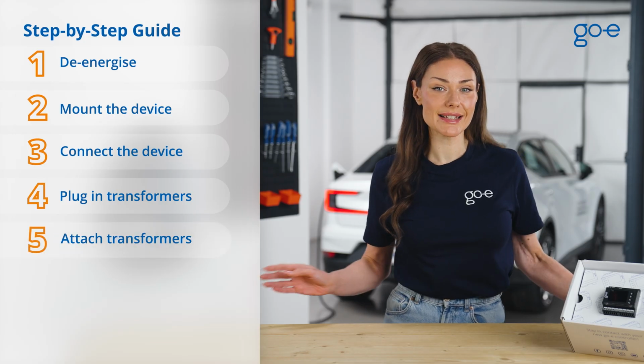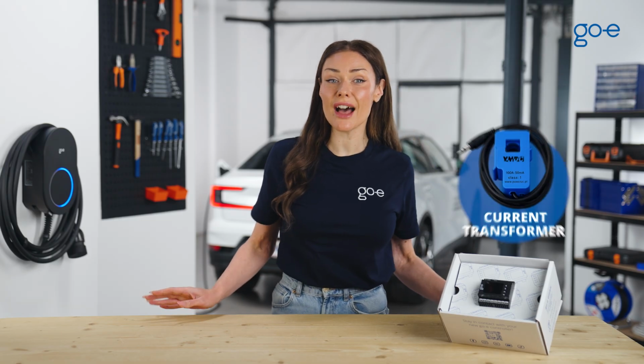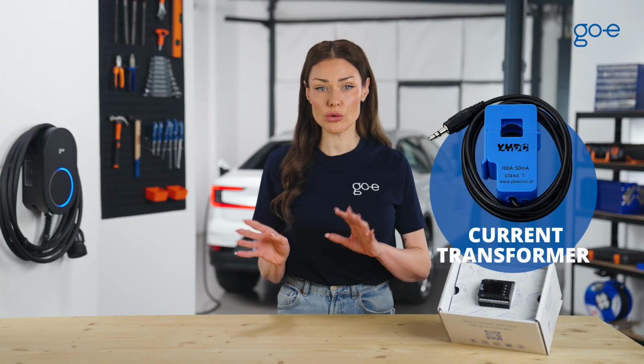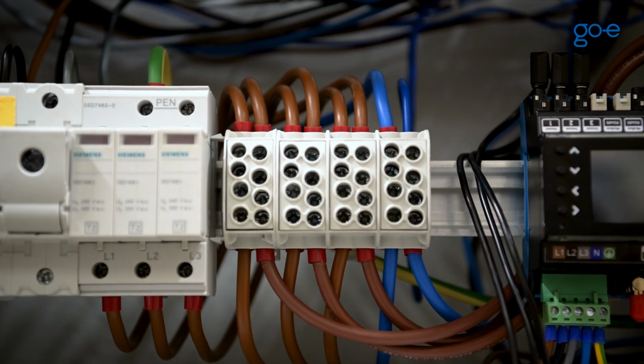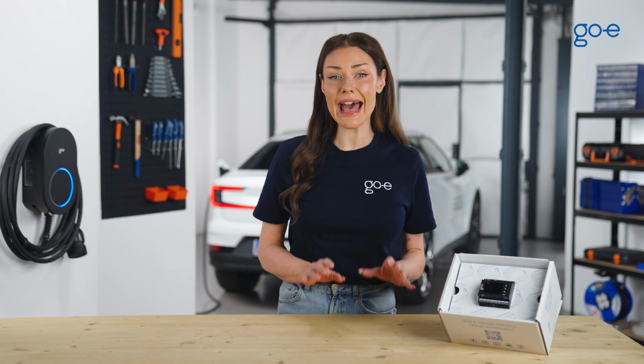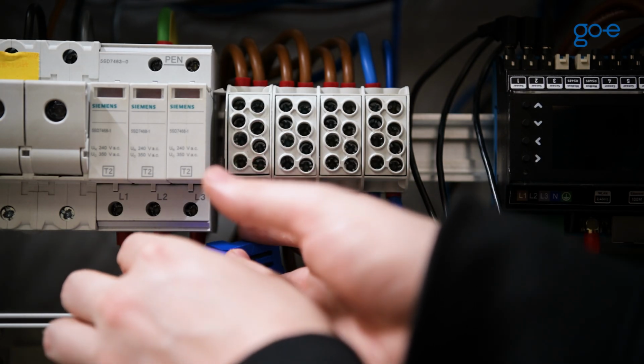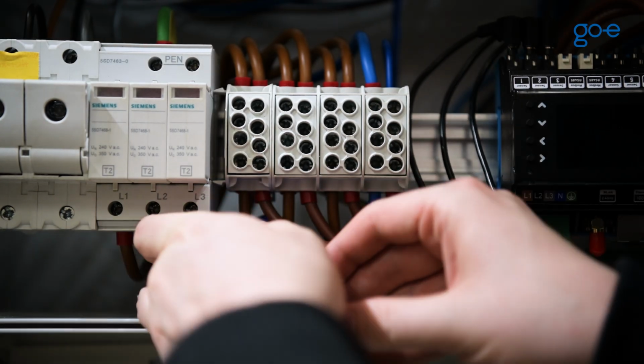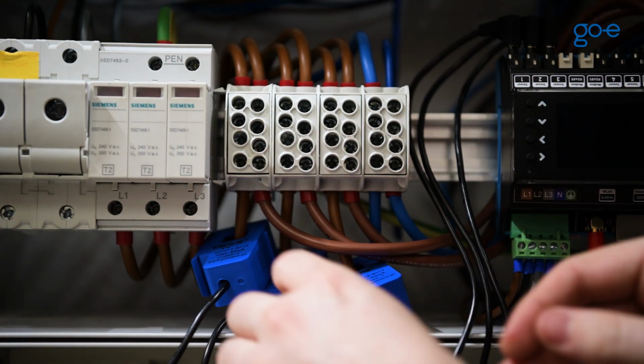Step 5. Next, attach the current transformers. For PV surplus optimization, we need enough sensors to measure the power going to and from the grid. The easiest way to do this is by measuring directly at the grid connection. However, it's also possible to measure the load branch and the PV inverter separately. The GoE controller can then add or subtract these values. In most cases, it's easiest to measure directly at the grid connection. Here we use 3 current transformers. Phase 1 connects to sensor 1, phase 2 to sensor 2, and phase 3 to sensor 3.